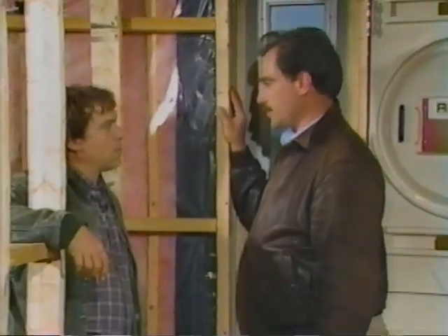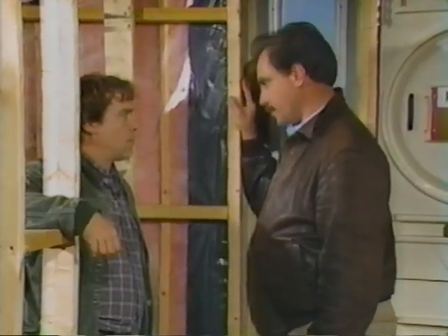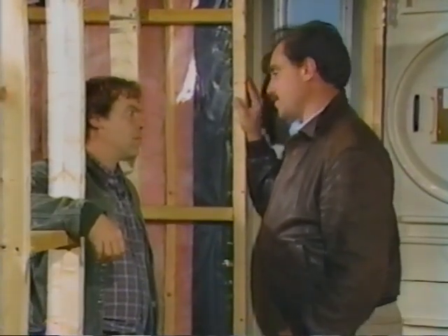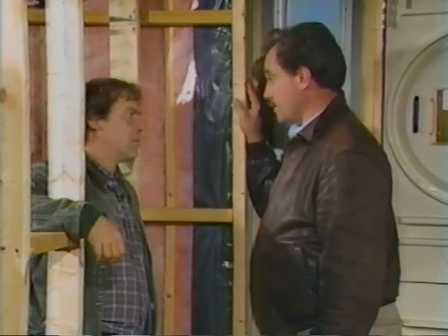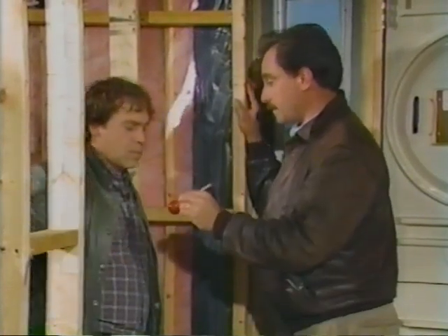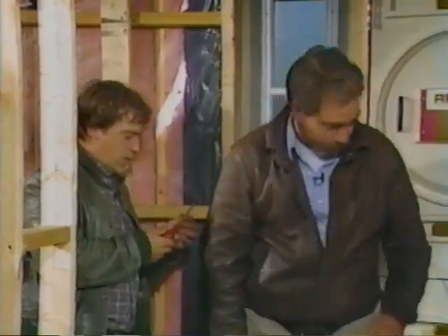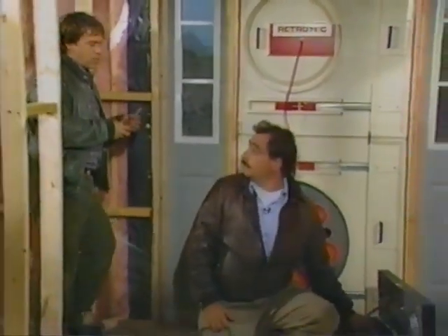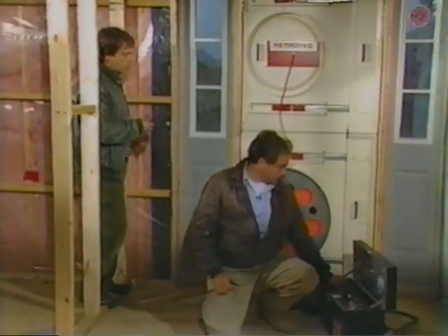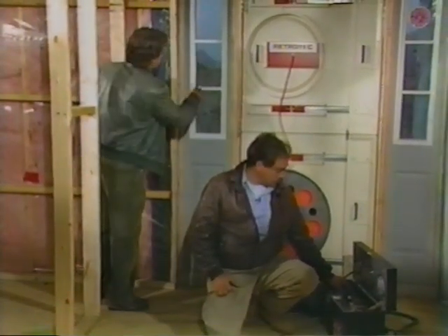David, this house has just been tested for the R-2000 pressure test, and it's passed. That means that this building is actually 6 times tighter than the house we were just in, and I'd like you to see if you can find any holes. Okay. I'm new at this. Do I wait for the fan to get way up to speed? Yeah, well, it's coming up right quick. There you go.